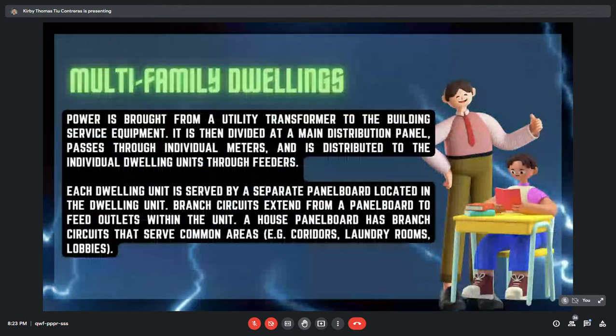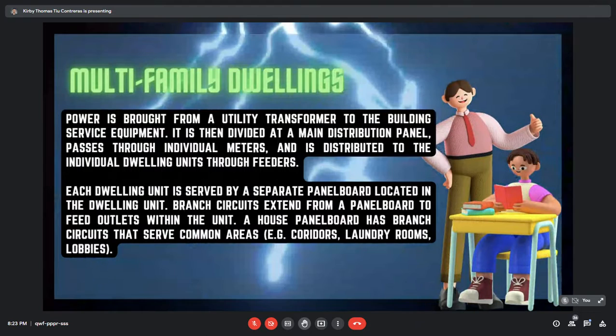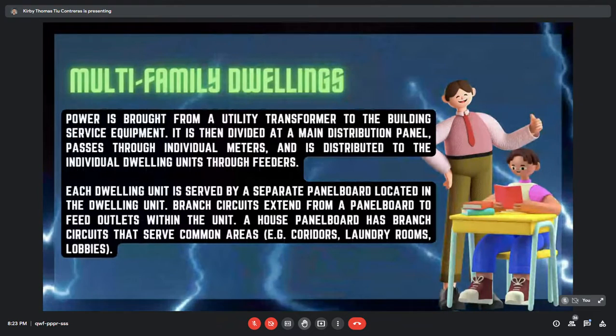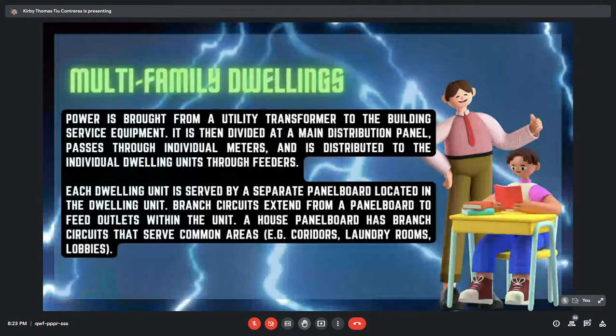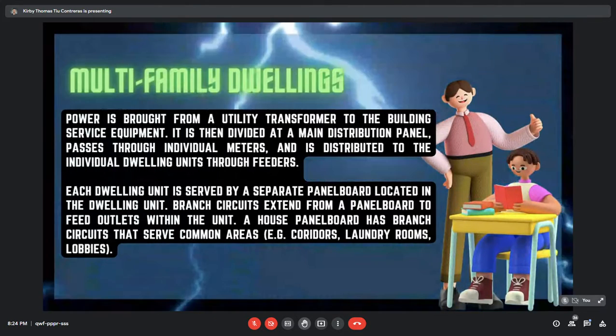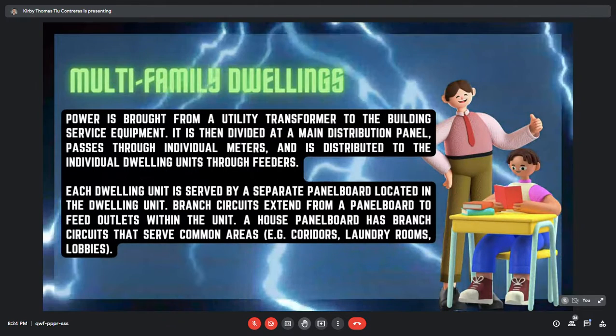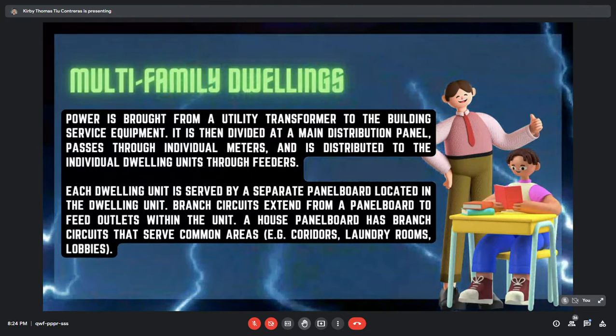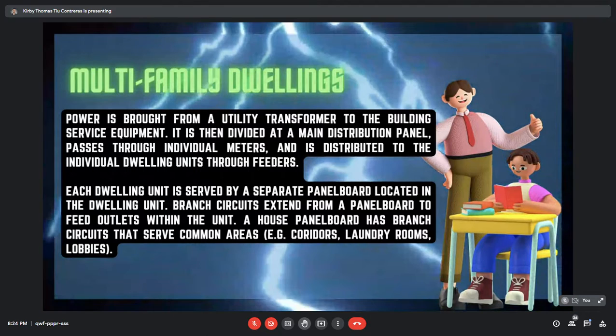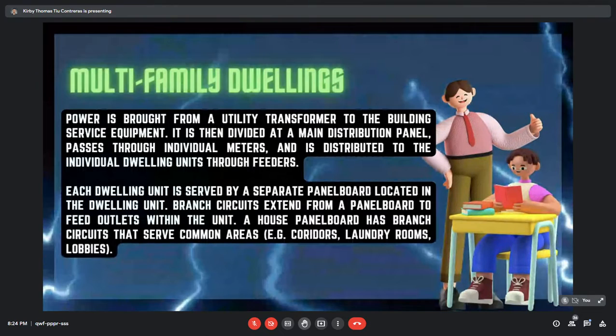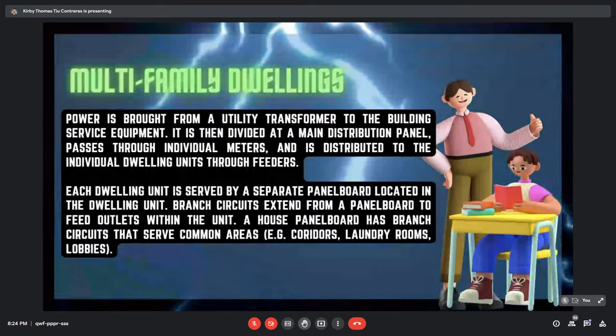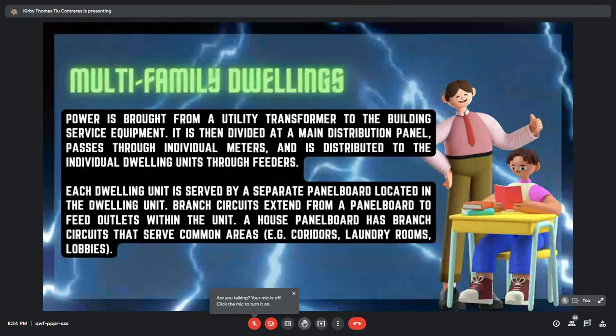So for the conclusion of my topic, the designs of the electrical systems vary from one building to another, depending on the design and purpose of the building and the components within the building. An industrial building, which is the next type, differs from both residential and business buildings because their electrical power requirements vary. And to avoid confusion, the sizing of branch circuits, feeders, and service conductors for multi-family dwellings is similar to the sizing for residential systems. We just size the feeders to individual dwelling units in the same manner. Also, to add another piece of information, apartment unit electrical power is distributed at 120 over 208 volts, three-phase, four-wire to maintain utility metering. So that's all for my topic.